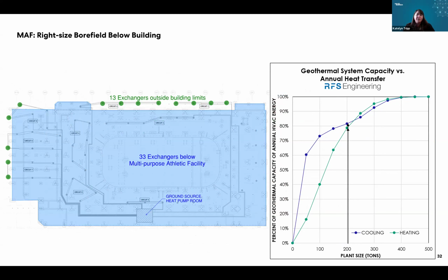The graph to the right was used to evaluate how much geothermal capacity should be targeted for the project. It shows on the y-axis the percent geothermal capacity to the annual HVAC demand. As the curve flattens out, there's less benefit to using ground source heat compared to alternate systems that Hillary outlined. So based on the load profile for this building, it was selected to use ground source heat exchange for 80% of the annual heating and cooling load, with supplemental systems for the balance. This approach helps right-size the bore field to balance the higher cost of the ground source heat exchange system and maintain the construction schedule.